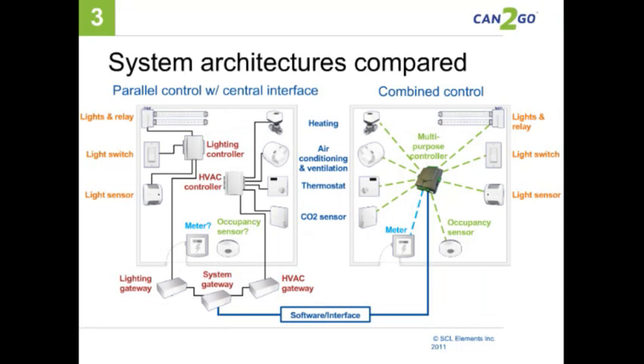And then you have the HVAC controller, which is talking to the actuators and to the VAV boxes, the thermostats, and CO2 sensors, for example. And then there are other things like metering and occupancy sensors. What do we do with the occupancy sensor? In traditional systems, sometimes you may actually need two: one occupancy sensor hooked up to your lighting control and another one for your HVAC. That's a lot of overhead. That's not always the case, but it is in some systems.